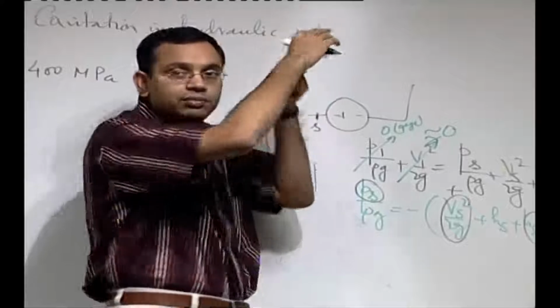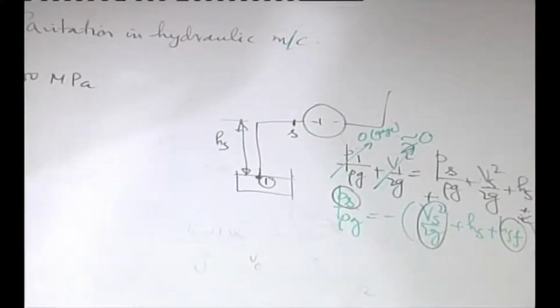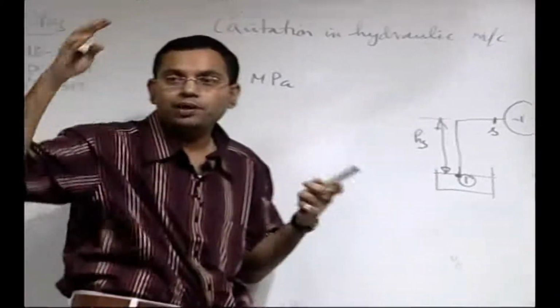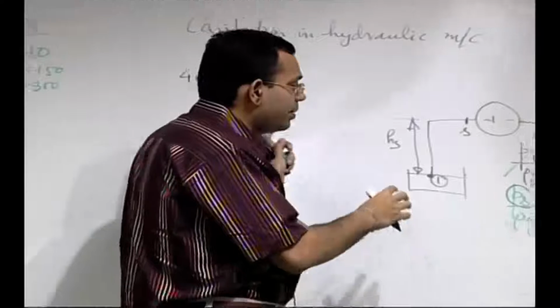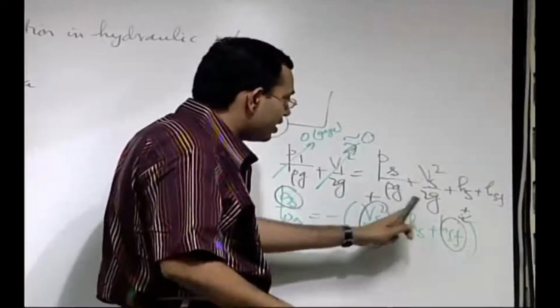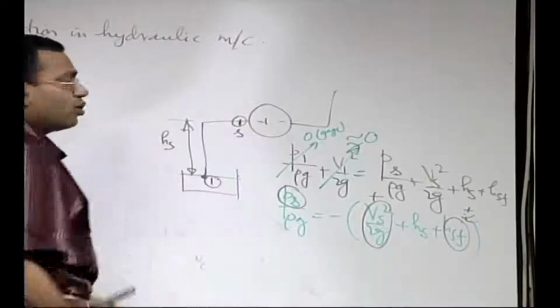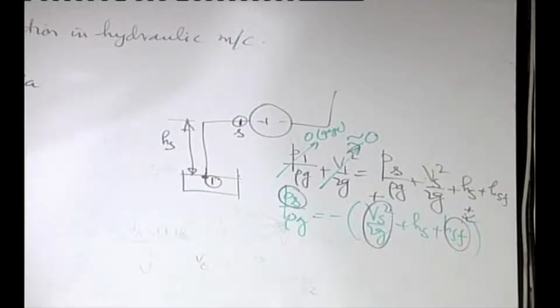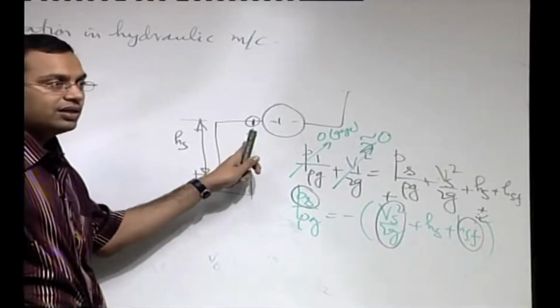In some cases, to avoid the strong negativity, the supply reservoir is put above the axis of the pump. In many industries, a classical example is a condensate extraction pump or maybe a boiler feed pump in a steam power plant. One has to keep in mind that no matter what Hs is, positive or negative, this is the location which is prone to very low pressure. So, we have to put a lot of attention on this one.